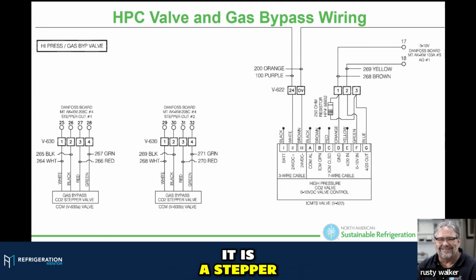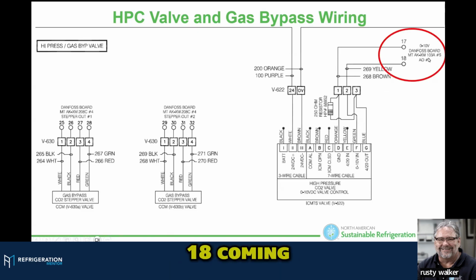It is a stepper, but I like to refer to this as an analog stepper, not a bipolar stepper or a unipolar stepper. And I'll show you why. Because coming right here, you see 17 and 18 coming off the controller. That's a 0 to 10 volt DC signal coming into these two pins off the yellow and brown wire. All right. And so if the valve says it's open 50%, I expect right here to read 5 volts DC. If this says 48%, I expect to read 4.8 volts DC. That tells me the controller is in charge.